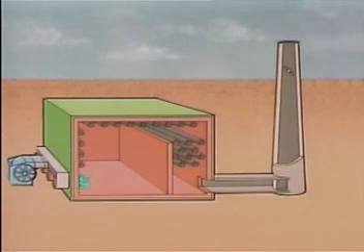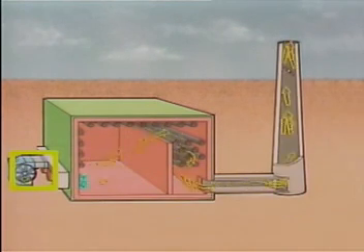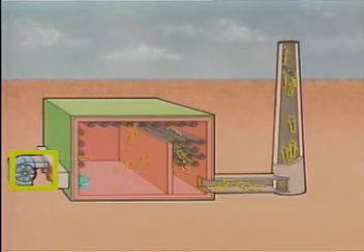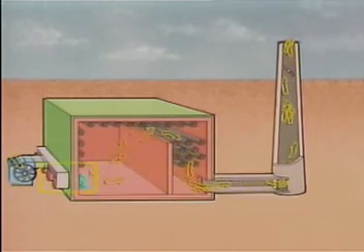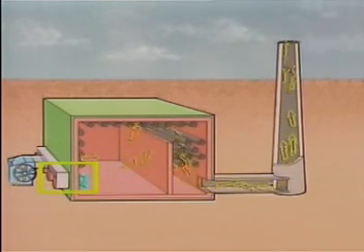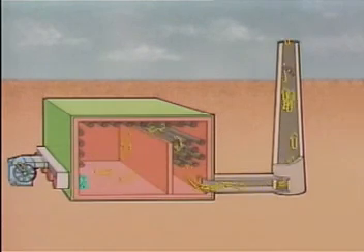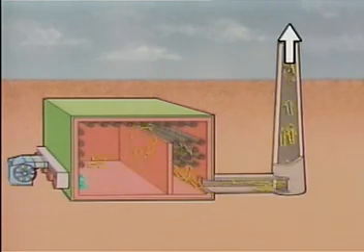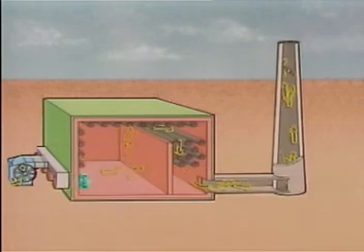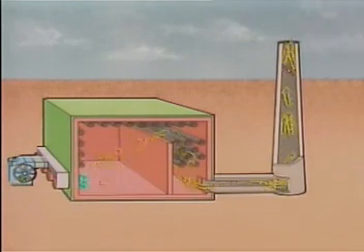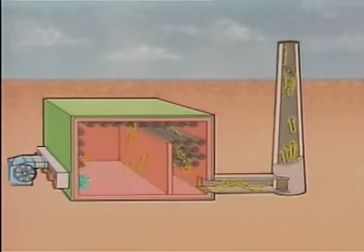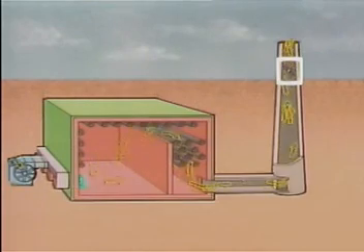This is a simplified illustration of a forced draft furnace. A fan, called a forced draft fan, draws air from the atmosphere and forces it into the furnace. On this furnace, the burners are mounted along one wall. The combustion gases flow through the furnace and then out through the stack. In a forced draft furnace, airflow is controlled by coordinating the positions and operation of the stack damper, the burner registers, and the fan.